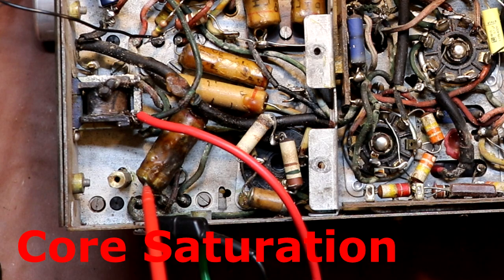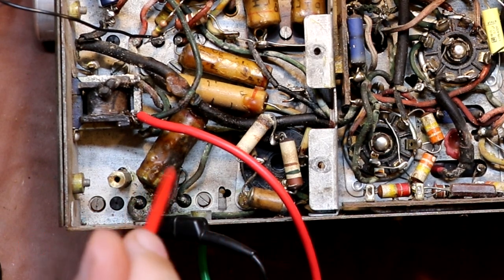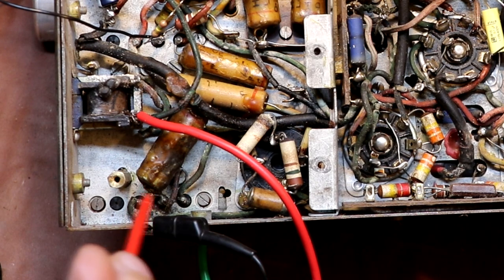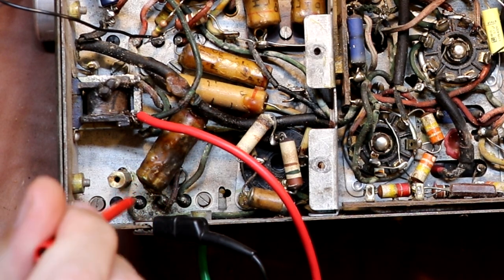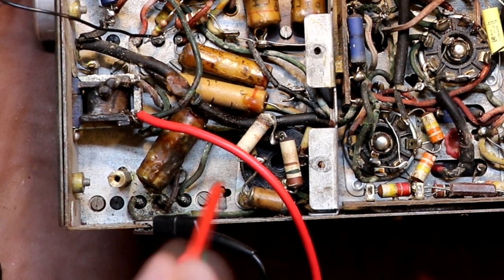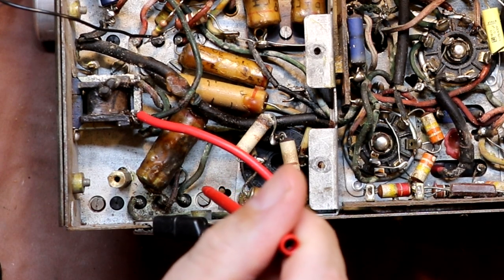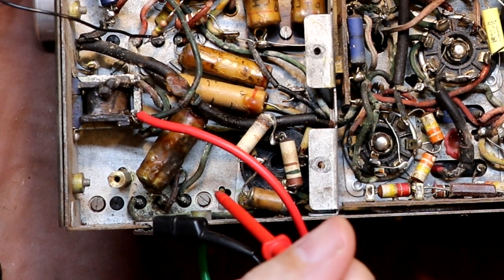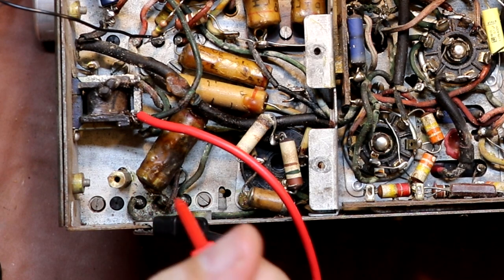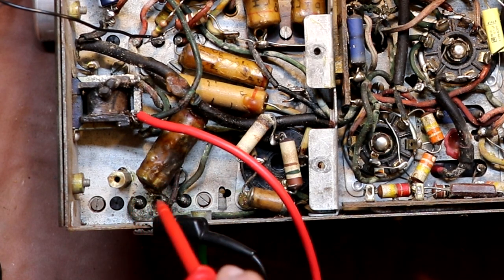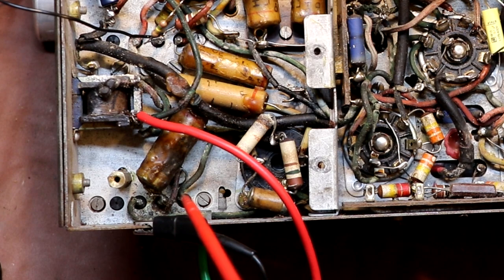The transformer would become magnetised, and as it becomes more and more magnetised, it becomes less and less efficient, to the point where it just wouldn't work anymore. So what they're actually doing is magnetising the transformer in one direction when they pull one of the windings to ground, and then magnetising it in the other direction when the other winding gets pulled to ground, constantly swapping from one winding to the other. That's what you need to do to make the transformer operate efficiently.